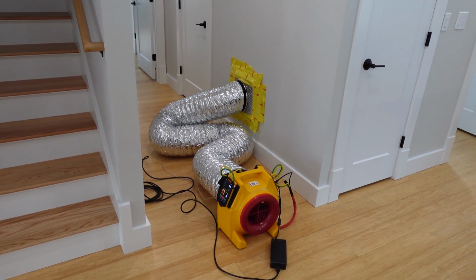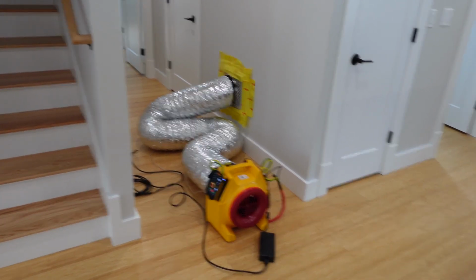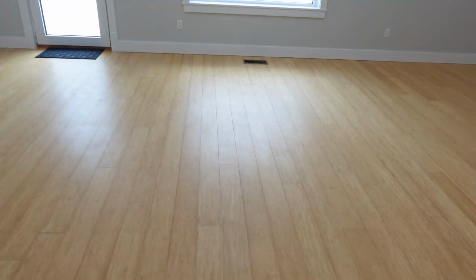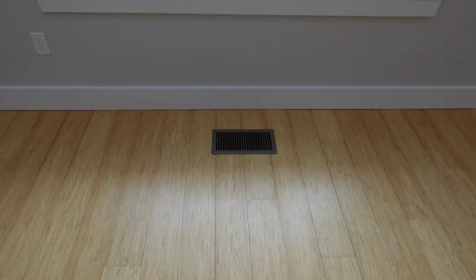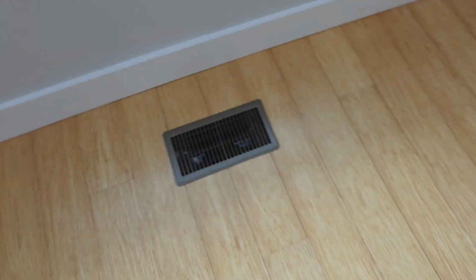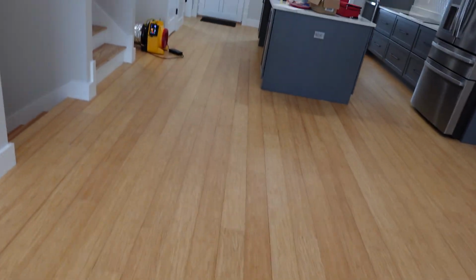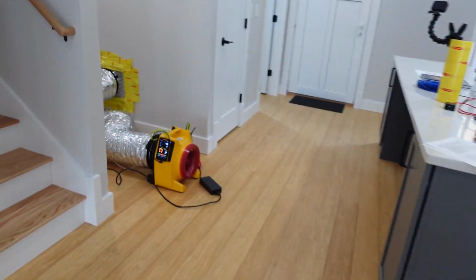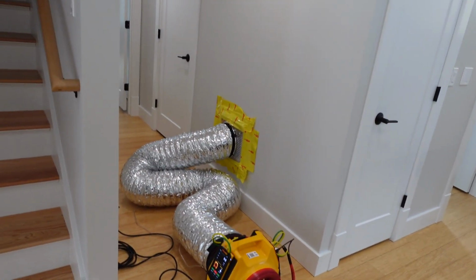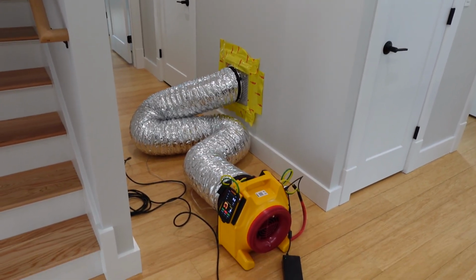Having a low airflow rate will reduce the amount of noise that's generated from the ductwork, because lower airflow will have less resistance. So I want to ensure that the system is running around 400 CFM on the low setting.